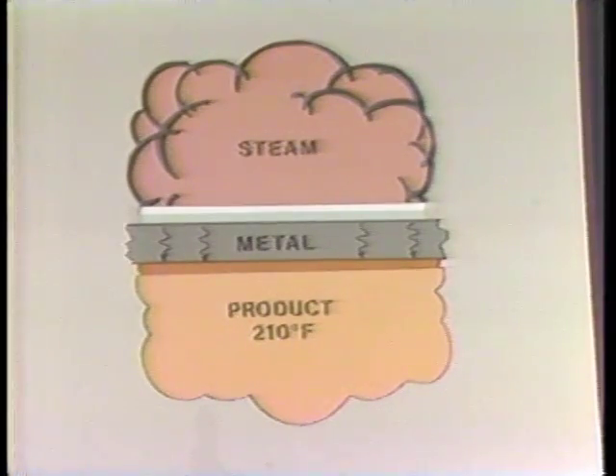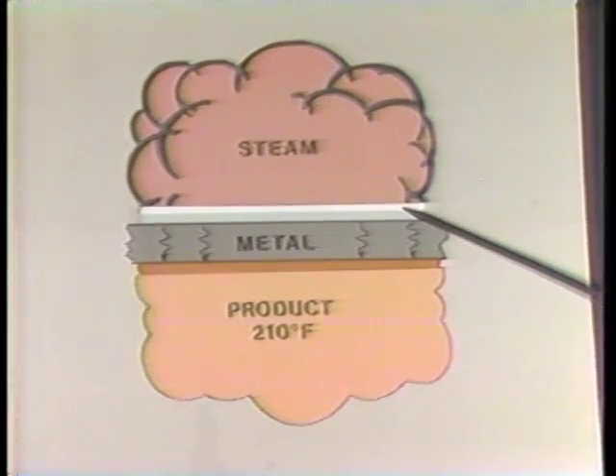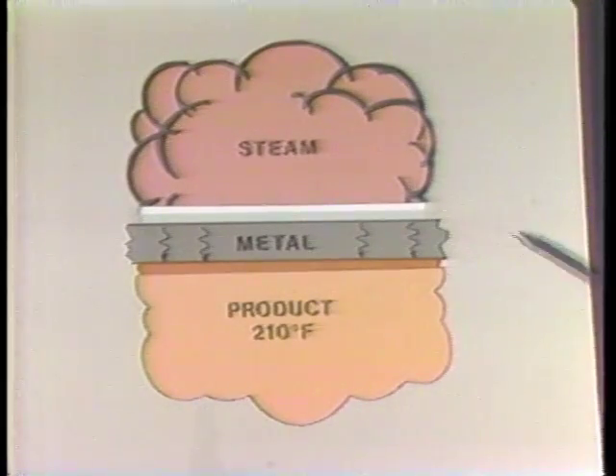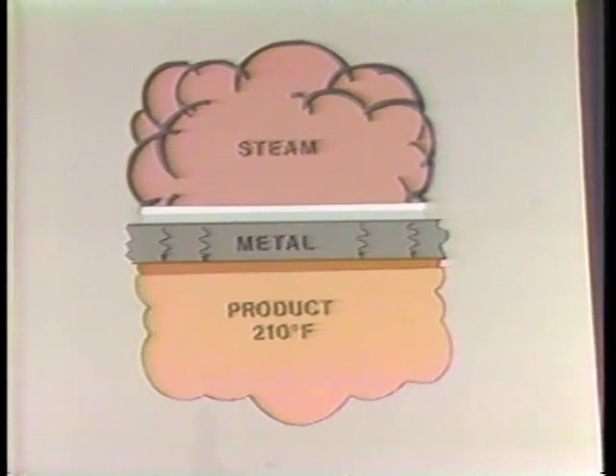If it were possible to reduce the thickness of the condensate and air on the inside of the surface by one-half, the steam pressure could be lowered from 15 to 10 pounds gauge, or 240 degrees Fahrenheit.